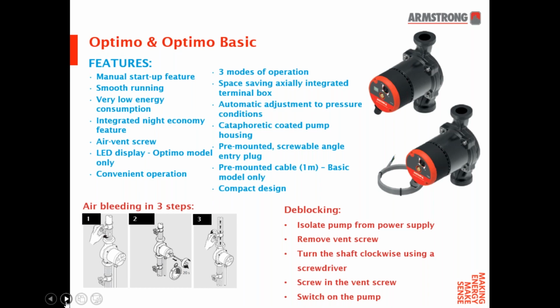A similar procedure is required if the pump needs deblocking. So isolate the pump from the power supply. You think it'd be fairly obvious, but we need to reiterate that. Remove the air vent screw completely, then place the screwdriver in the shaft, turning it clockwise. Put the screw back in the screw vent and switch the pump back on, and that should de-block both of those circulators if required.